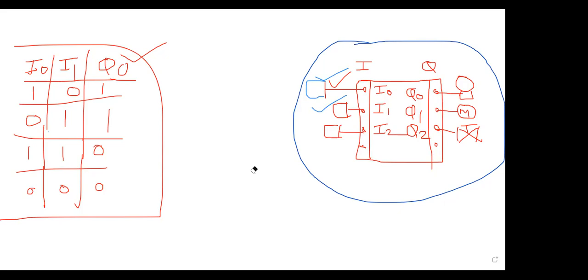You are trying well. I told Vilas sir, we should have only one coil. You have taken 3 coils. We should have only one coil. Very good. But Vilas sir, you check one more thing, that when you don't press any switch, supply should not reach the coil. That is also you need to check. Very good try.